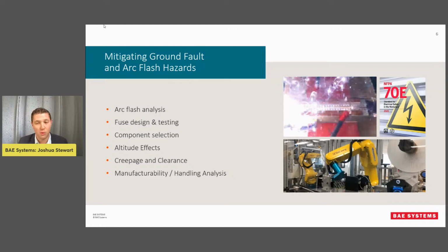So if I can just give an example, you might design a battery pack, and the fuses are designed so that the short circuit current opens the fuse at room temperature. But then you take the same battery pack and you take it down to freezing temperatures. And what happens is the internal resistance of the battery cells actually increases as the temperature decreases. And so now what you have is the same battery pack, but its short circuit current is lower than what the fuse will clear at. So now you have a sustained arc flash taking place on the same battery pack with a fuse that will not clear.